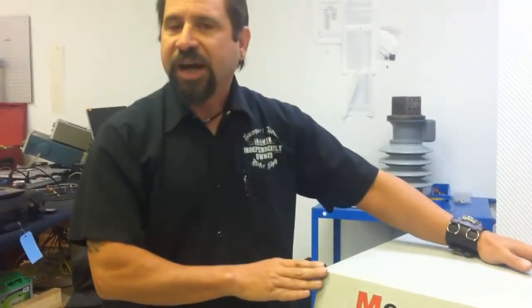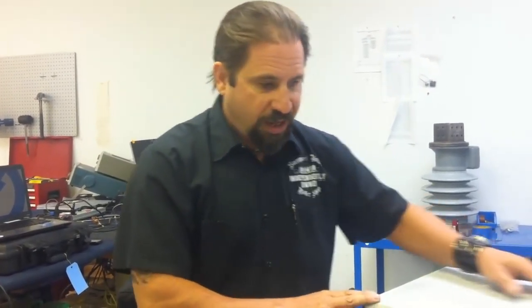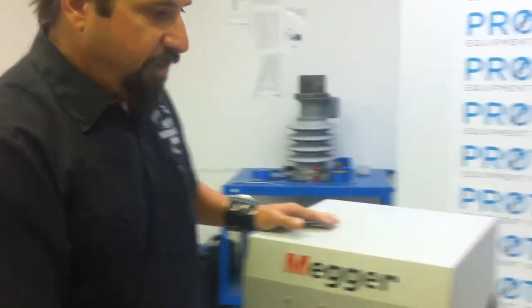A system of this size is ideal for basically 15,000 volt type cabling services, up to about 25,000 volt cabling services. It is also very useful for large industrial or potentially wind farming applications where we get cable faults or breakdowns in the buried services.